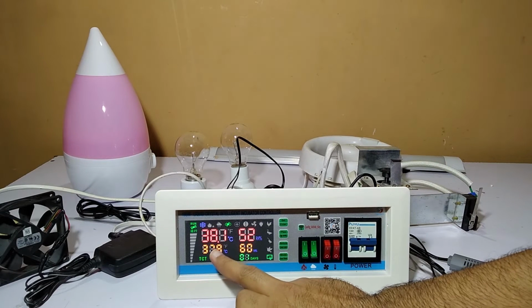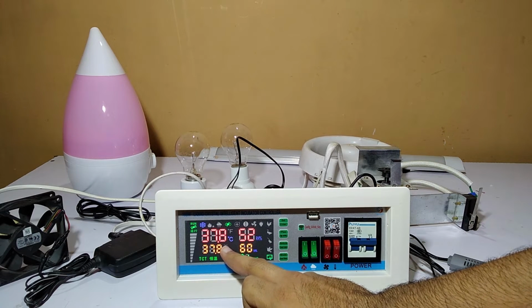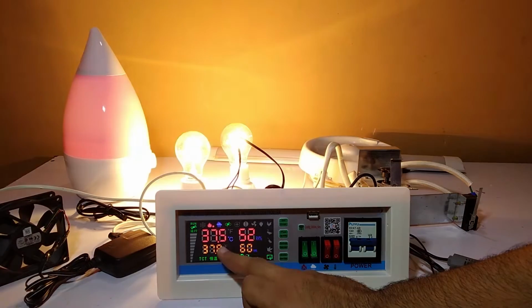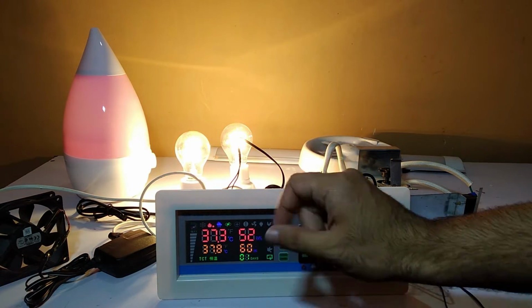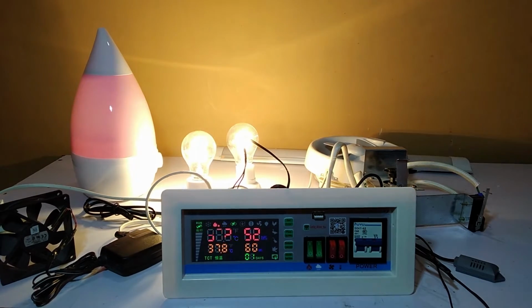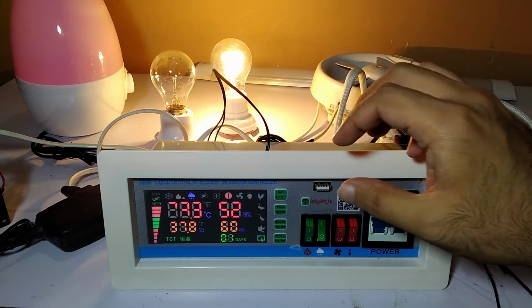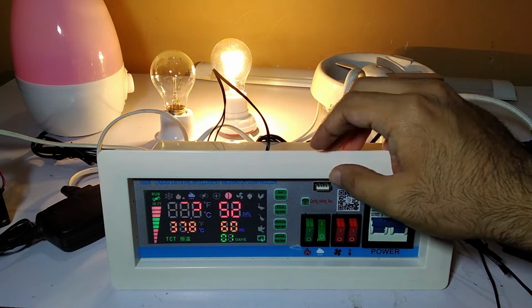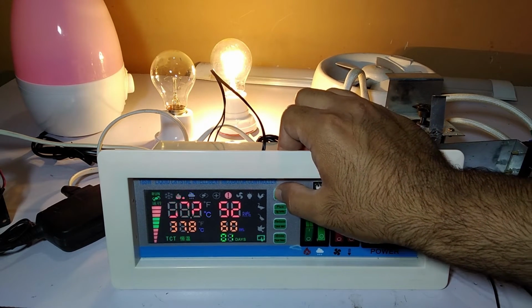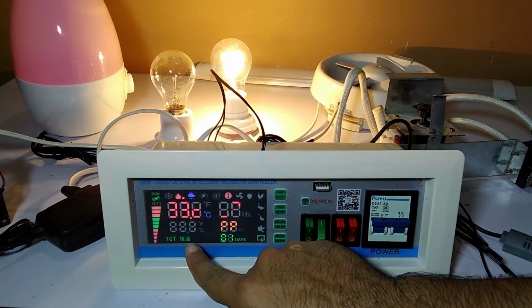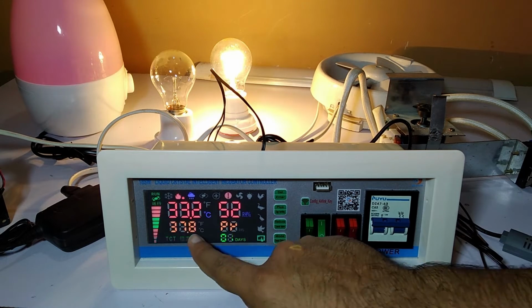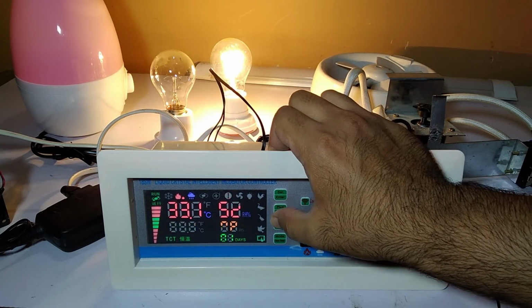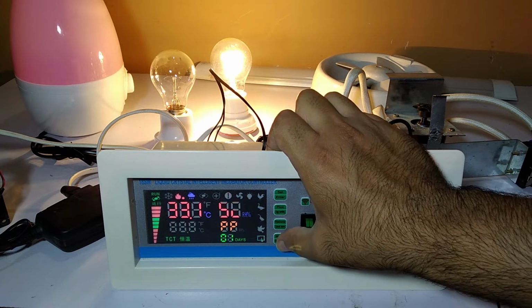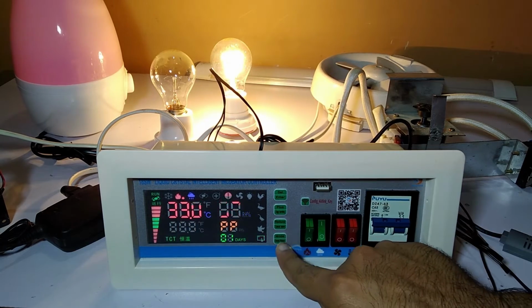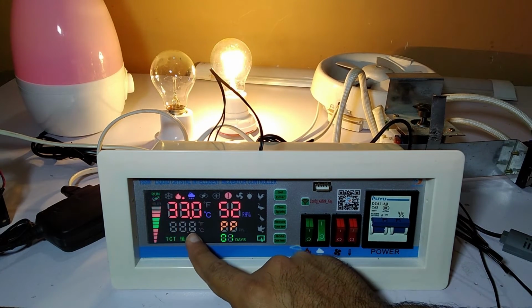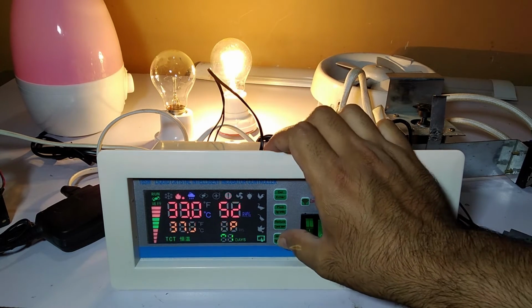When it reaches 37.5, it will turn off the exhaust and turn on the heater again. For setting the temperature and humidity, you have to press the set button one time and it will blink. When it's blinking, you can press up and down and then press mode, and then it will go to 37.9.